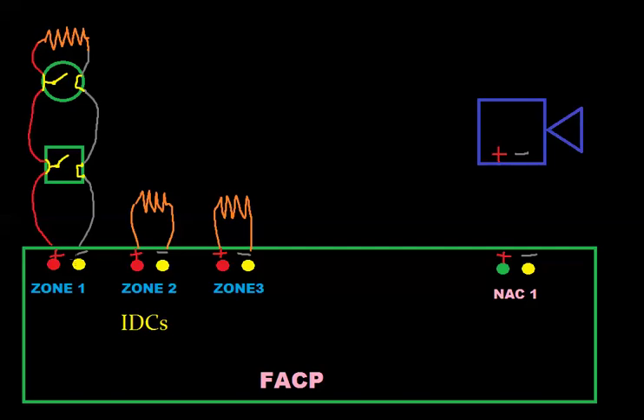So I redrew a fire alarm panel here, a conventional one, with three zones and one output. This zone has two devices on it, let's say a pull station and a heat detector. The other two zones are bypassed. Since the zone wants to see a resistor, you bypass it by just putting a resistor on that terminal. It doesn't know if there's 100 pull stations on a zone or just an end-line resistor.